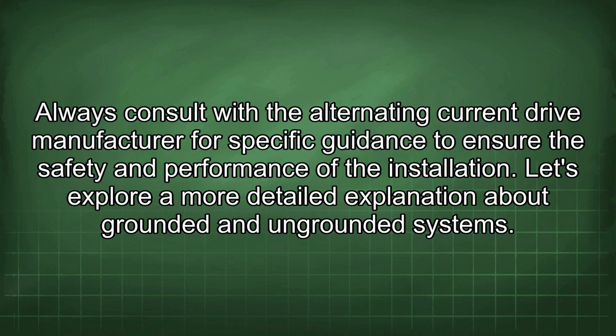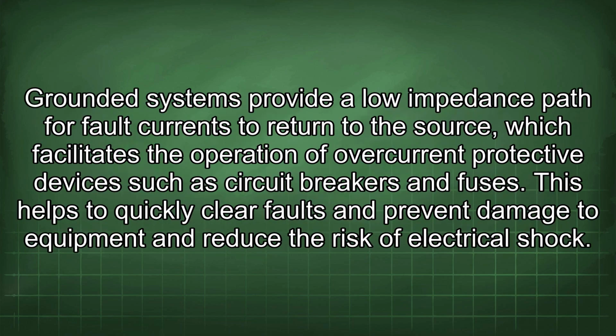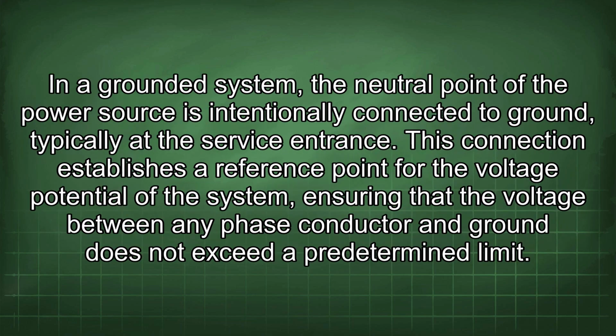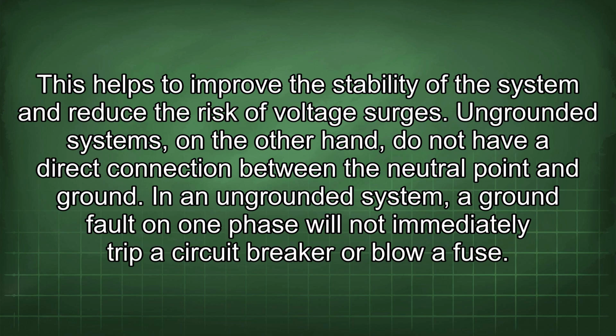Let's explore a more detailed explanation about grounded and ungrounded systems. Grounded systems provide a low impedance path for fault currents to return to the source, which facilitates the operation of overcurrent protective devices such as circuit breakers and fuses. This helps to quickly clear faults and prevent damage to equipment and reduce the risk of electrical shock. In a grounded system, the neutral point of the power source is intentionally connected to ground, typically at the service entrance. This connection establishes a reference point for the voltage potential of the system, ensuring that the voltage between any phase conductor and ground does not exceed a predetermined limit. This helps to improve the stability of the system and reduce the risk of voltage surges.